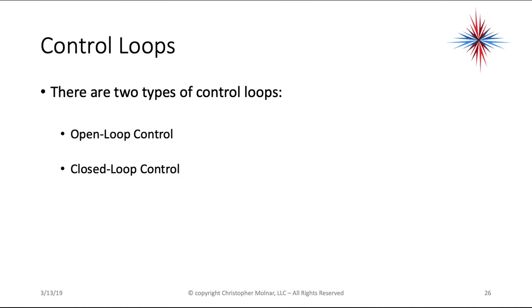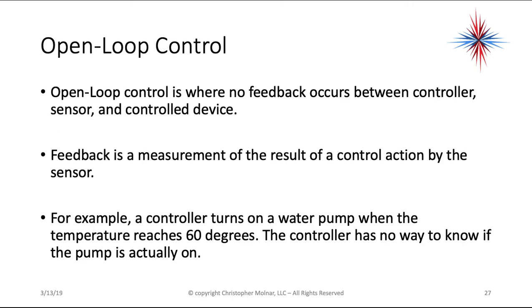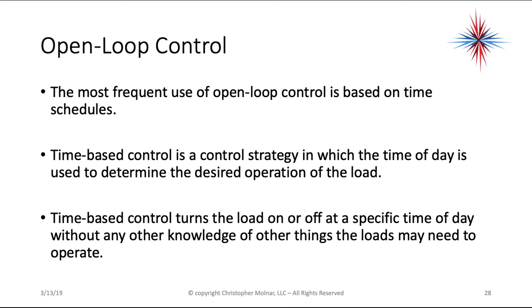There are two types of control loops. Open loop control is where there's no feedback occurring between the controller, sensor, and control device. Feedback is a measurement of the result of a control action by the sensor — for example, a controller turns on a water pump when temperature reaches 60 degrees, but has no way of knowing if the pump is actually on. The most frequent use of open loop control is time-based scheduling, which turns loads on or off at specific times without knowledge of other operating conditions.